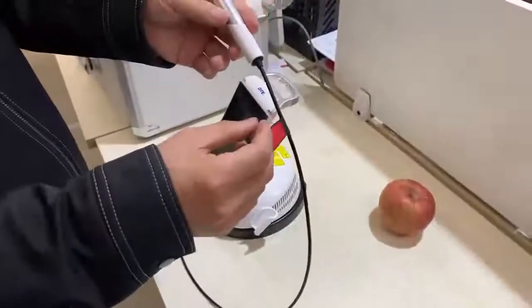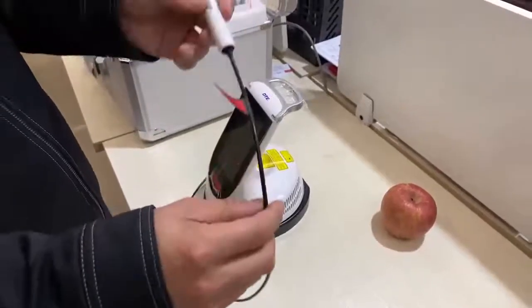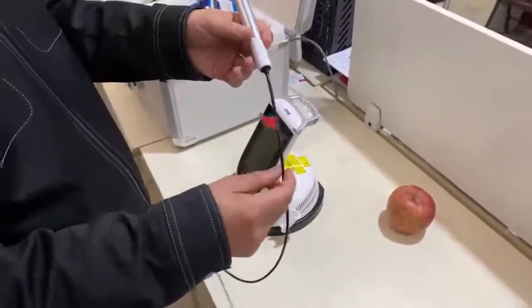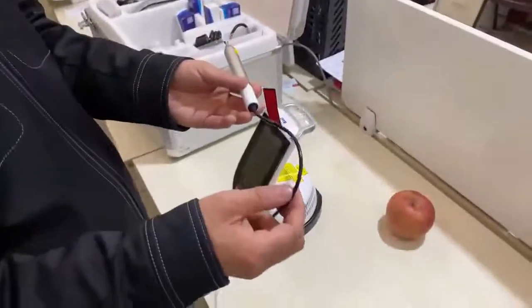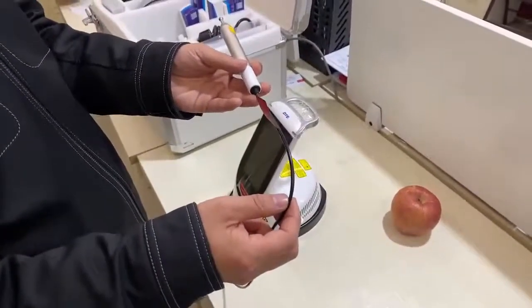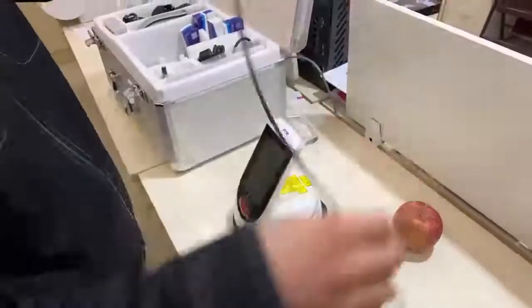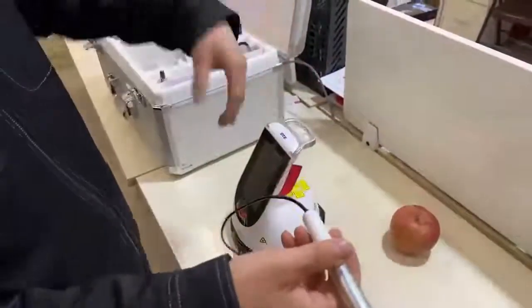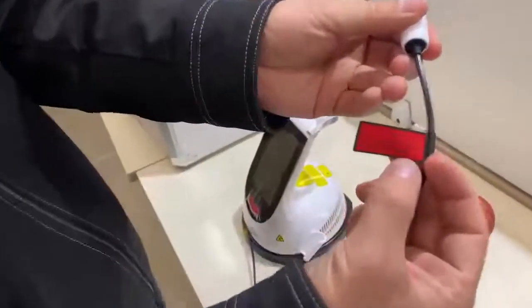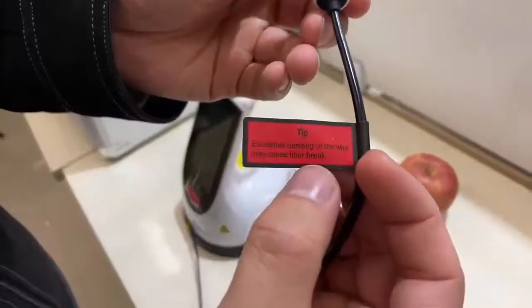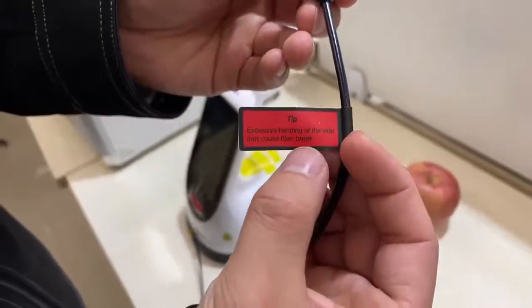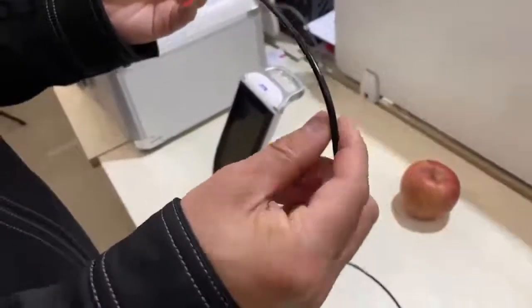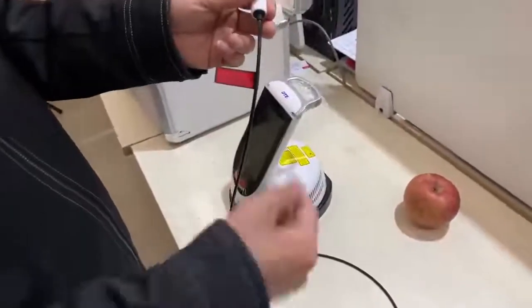And also we can see the handpiece cord, and pay attention. There is optical fiber inside the cord, so we cannot bend the cord too much, otherwise it will get broken. And if you break the handpiece cord, you have to replace the whole handpiece. And also we can see a tip here. It means we cannot bend the handpiece cord too much. So pay attention. Don't bend the handpiece cord too much, otherwise it will get broken inside. Okay, so this is about handpiece.